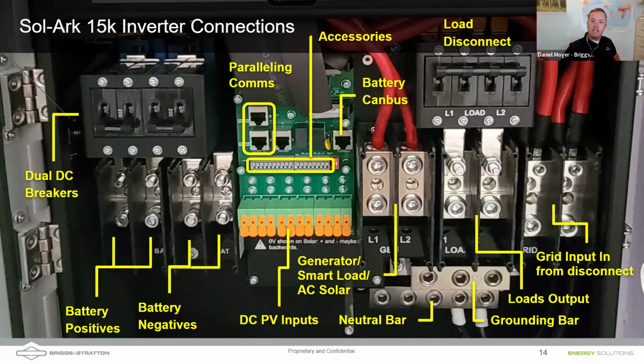You got a load disconnect. Down at the bottom right, we have our neutral bar, our ground bar. We have our parallel comms. That's where if we have multiple inverters, we would allow the inverters to talk to each other through there. Battery CAN bus is where we're going to talk to our SimpliPHI 6.6. We got the accessory pinouts. We'll go over those in a deeper dive in a second. Solar MPPT charge controllers. You got 3 of them down along the bottom. That's the little orange tabs there.